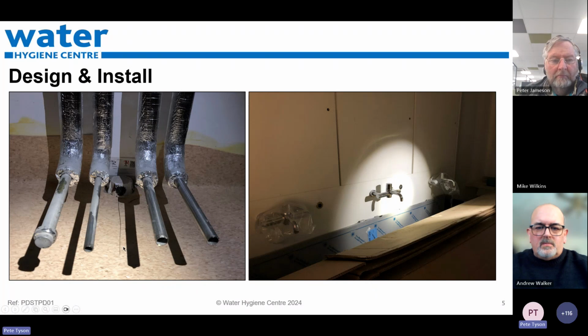And we've also got a little view here of some pipework that's been capped off. There's no potential for contamination on this particular one, but here, here, and here, they also need to be capped off and remain free. So open ends on pipework and components that are not kept sealed will invariably suffer from ingress of debris and contamination. So this is just a bog standard site that we've come across partway through an installation process.